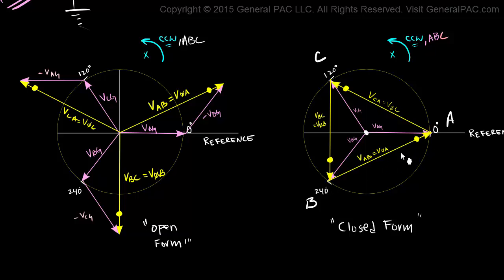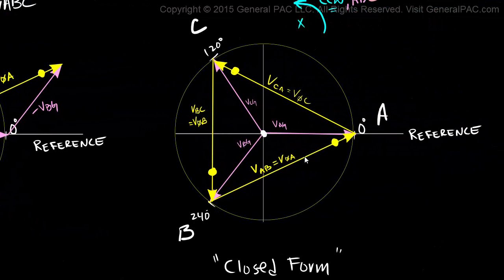We've defined this phasor here as V Phase A, and we said that the dotted side is the polarity side of V Phase A. Now look at what the polarity side of V Phase A is connected to: it's connected to the non-polarity side of V Phase C. Then the polarity side of V Phase C is connected to the non-polarity side of V Phase B. And the polarity side of V Phase B is connected to the non-polarity side of V Phase A.